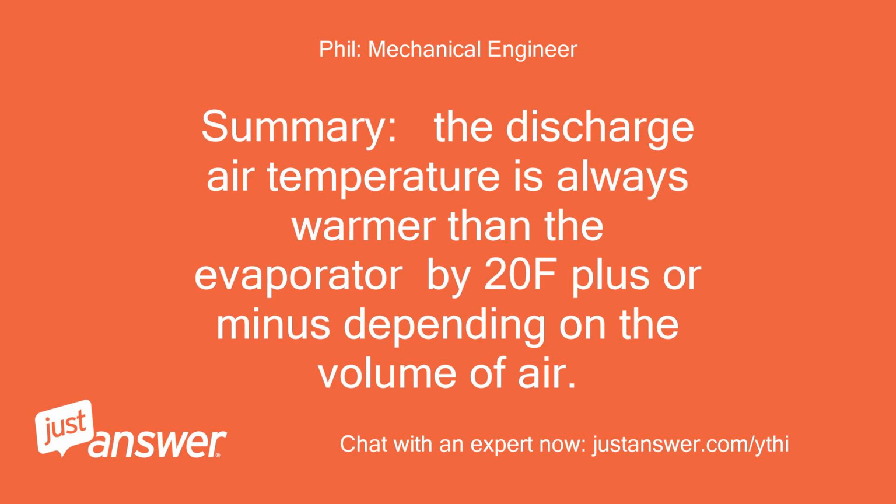Summary: the discharge air temperature is always warmer than the evaporator by 20°F plus or minus depending on the volume of air.